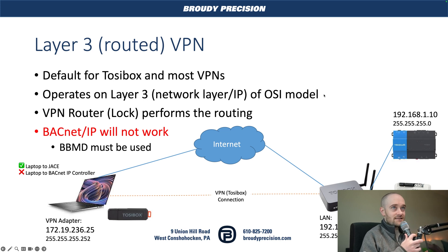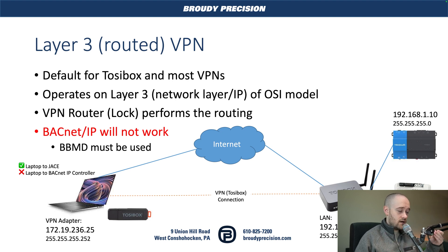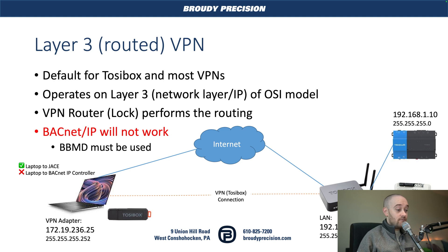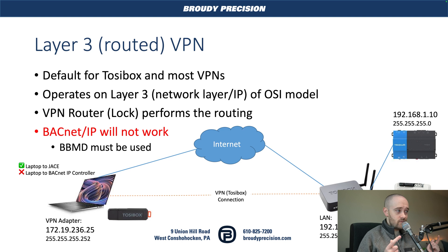We're going to start out with the default settings on a Tosibox. Most VPN solutions are going to default you to this style of doing things. It works great 99% of the time, but if you're using BACnet IP, you will run into issues with the way that you connect to your BACnet IP devices on that remote network — they just won't work. That's because BACnet IP relies a lot on broadcast communications, and broadcast communications only work on your subnet. Routers will not route broadcast packets intentionally, because obviously big problems could happen, so they intentionally don't do that.